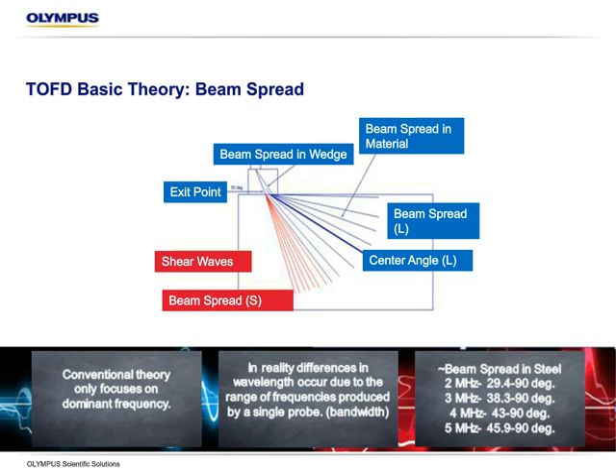in two different ways. First of all, when we basically pulse the instrument, the sound goes through the wedge. We have beam spread that occurs inside that wedge. And then once that sound goes through the coupling material into the actual material we're testing, we get another effect of beam spread. So we actually get a good manipulation of beam spread, which allows us to use a very small transducer and get a very wide volume of coverage that is very useful and one of the main benefits of time-of-flight diffraction. So we actually also have different wave modes. So we can see here, if we use a TOFD, we're using longitudinal waves.